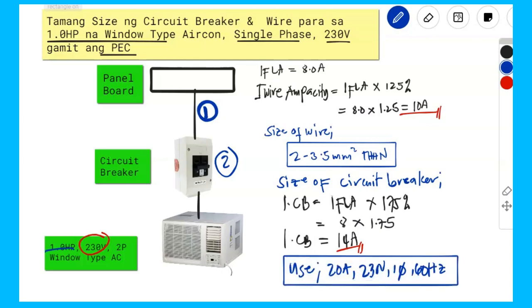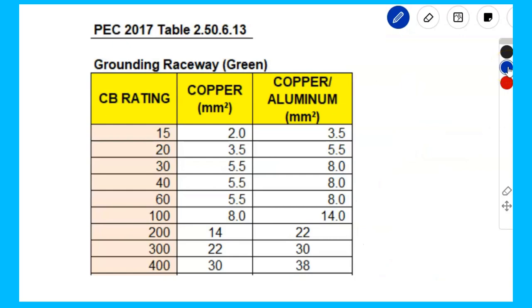So ang tanong, paano uli mag-size ng ground? Okay, so meron na tayong size of wire, and then wala pa tayong size ng ground. So, basahin natin uli sa Philippine Electrical Code, coming from the PEC 2017 table 2.50.6.13. So grounding raceway, ang kulay dapat is green, pag neutral that is white. So from this column, ito yung CB rating. Ang gamit natin is copper. Pag ang gamit mo is copper wire, ito yung reference mo. Pag ang gamit mo is aluminum, ito ang gamit mo. So sa ating example, ang gamit natin is copper wire.